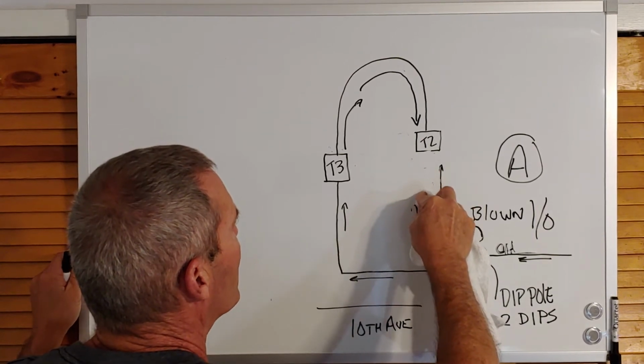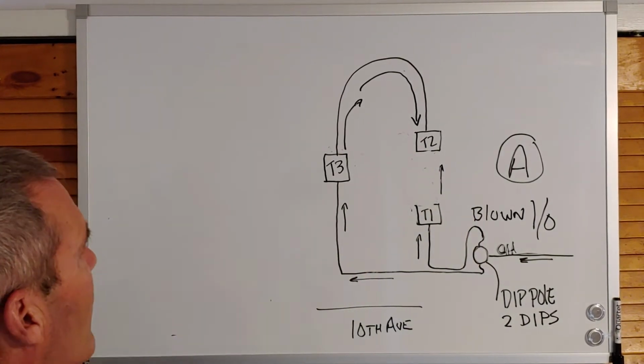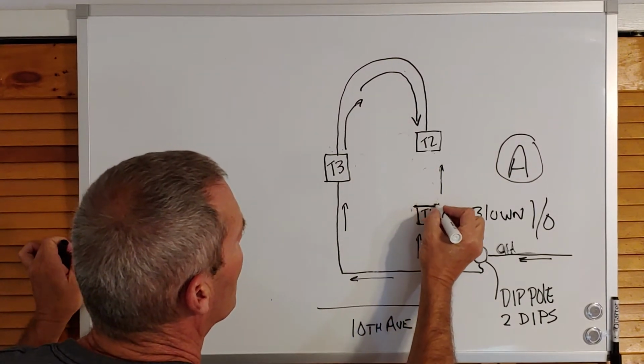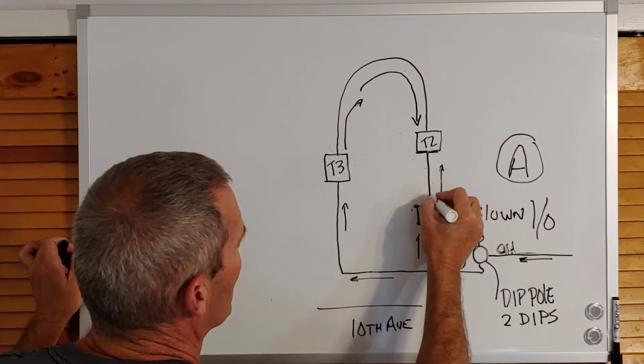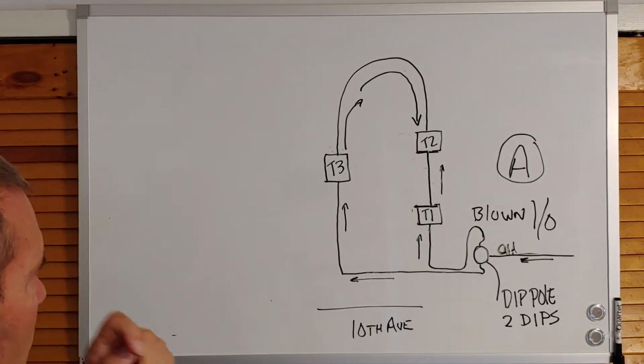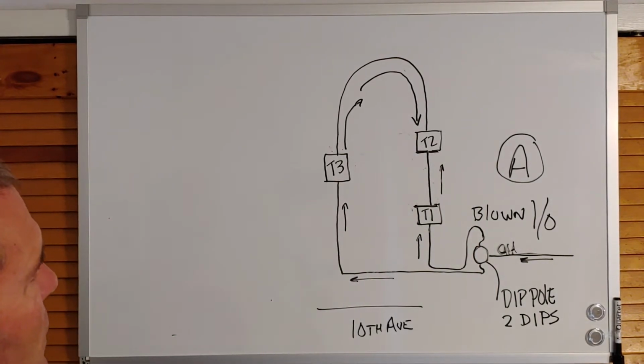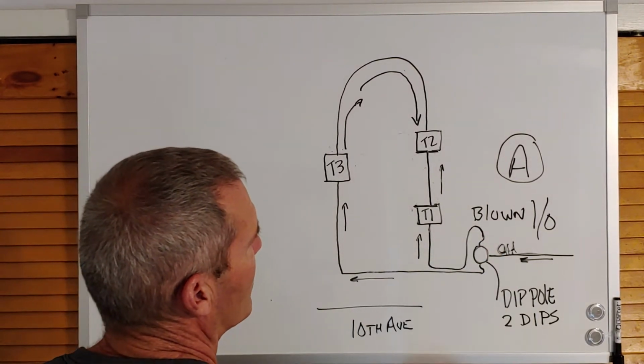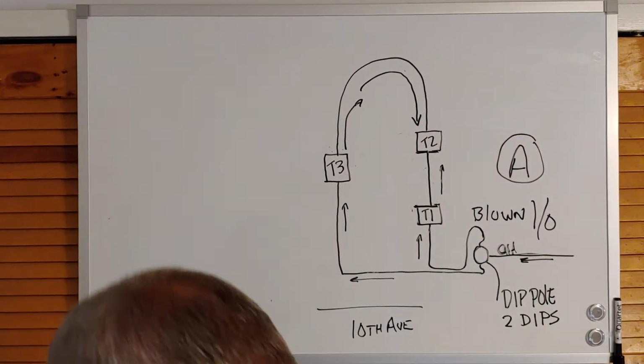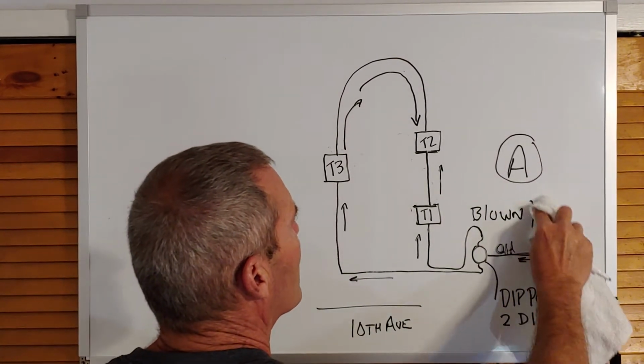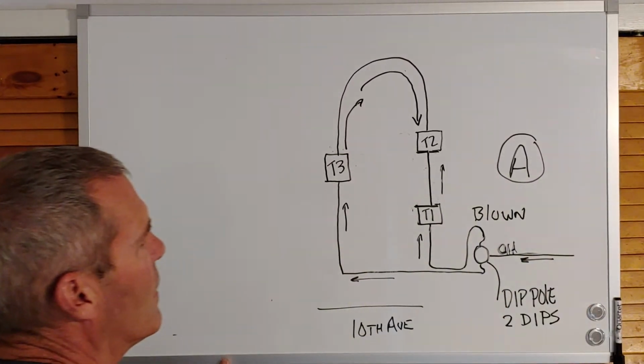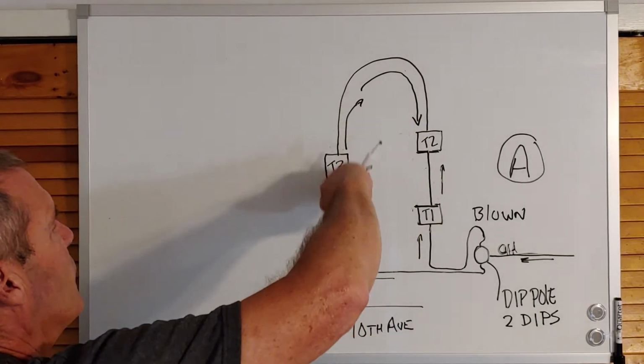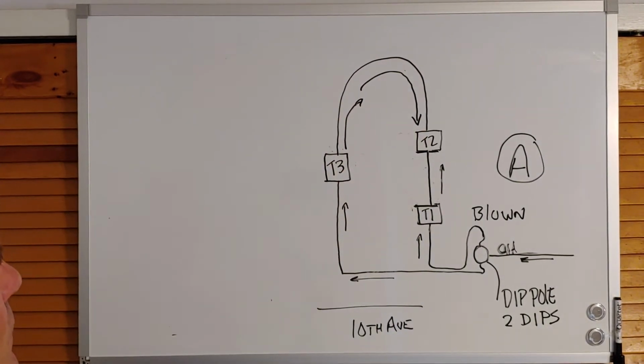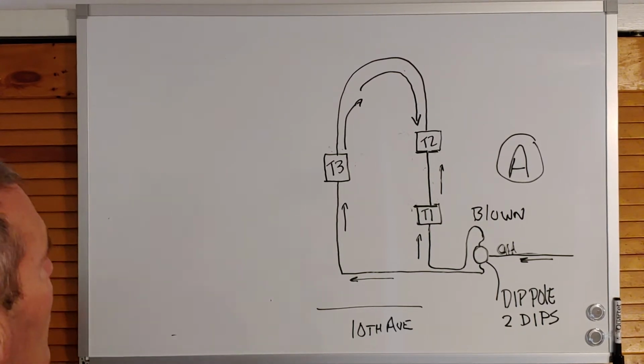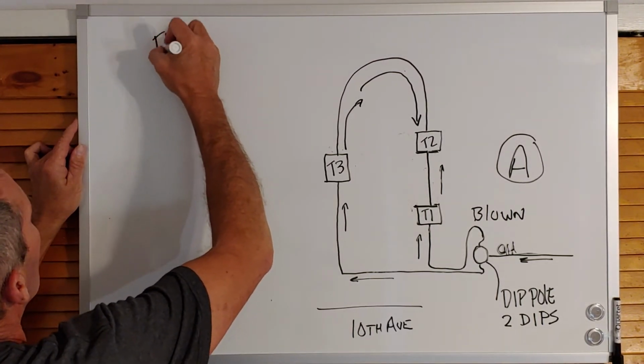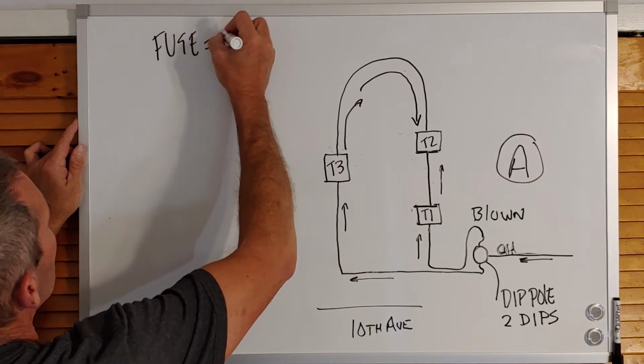Now, high potting, there's a lot more work involved. We're going to use the same scenario in this situation. We drive up, same fuse is blown, okay, and it is on single phase. We have no fault indicators in our system here whatsoever in our underground loop. The fuse blown equals our first indicator.